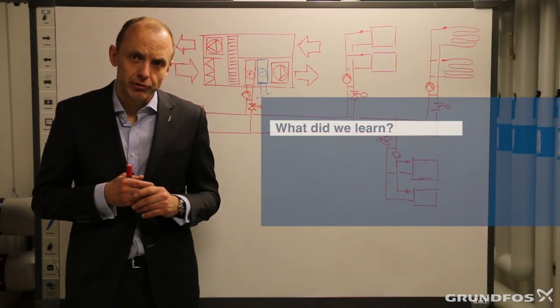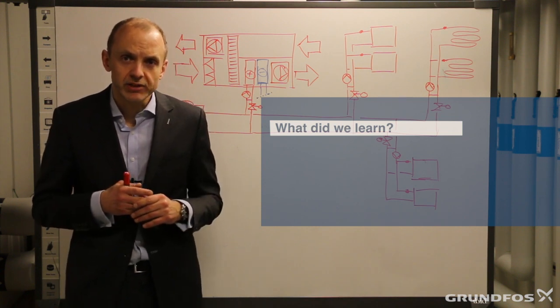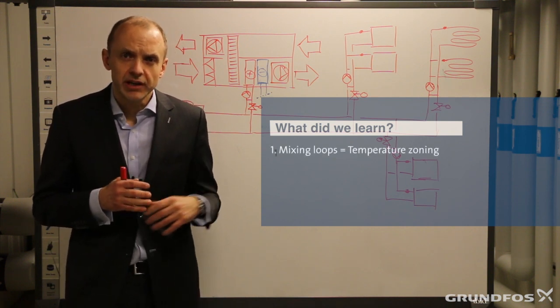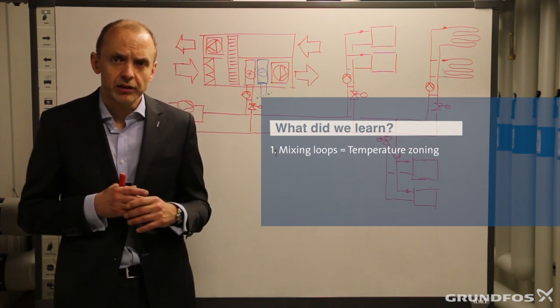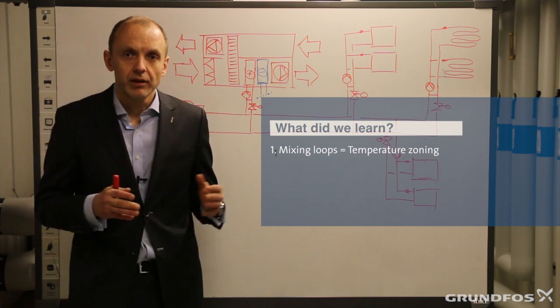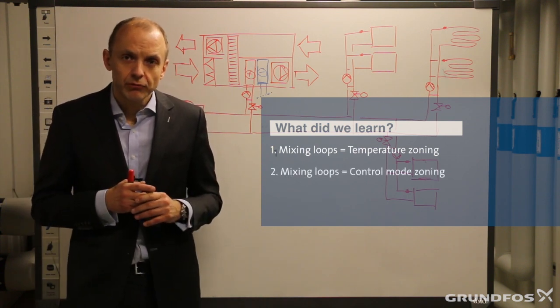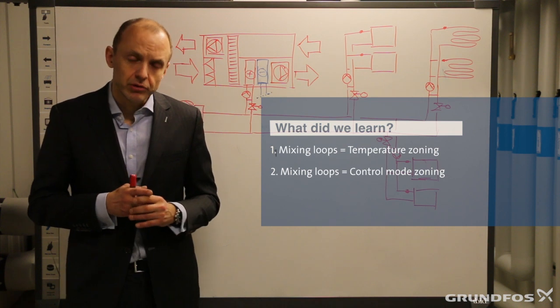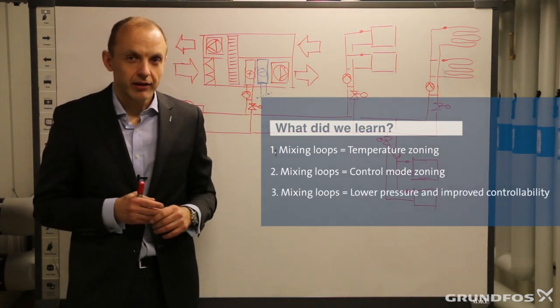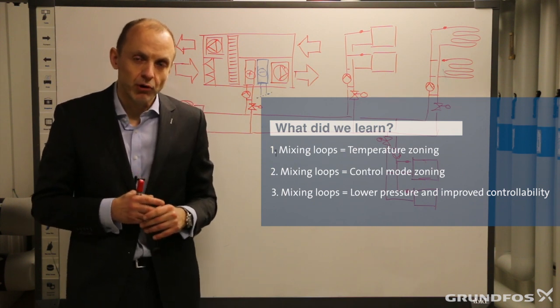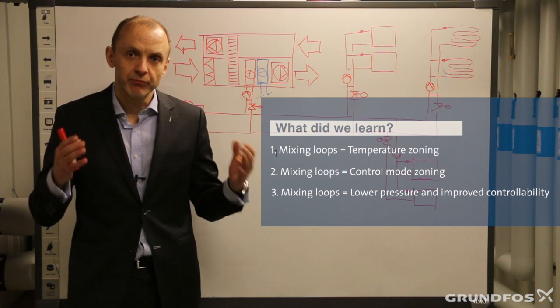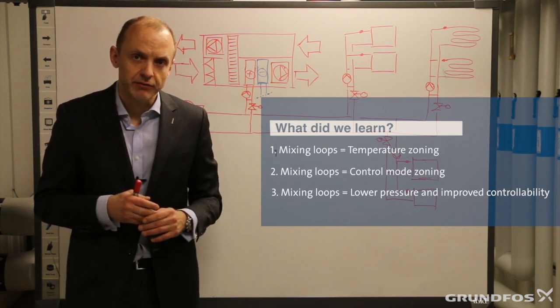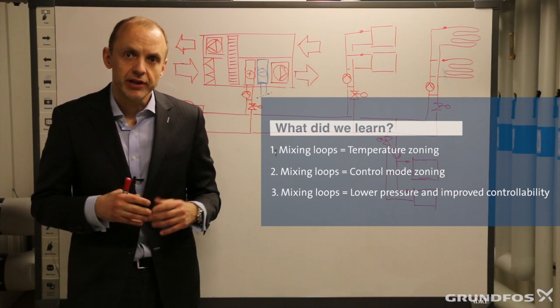So let's recap what we learned. Zoning of an HVAC system with mixing loops gives us a number of advantages. One is that we can run with different temperatures — we are not only dependent on the temperature provided by the boiler. Secondly, we can run with different control modes; every time we have a mixing loop, we can have a new control mode. Thirdly, with mixing loops we are able to reduce the overall differential pressure in the system because we have more pumps. That gives increased controllability of the whole system and saves us energy and money.